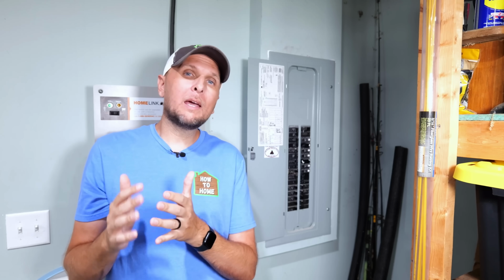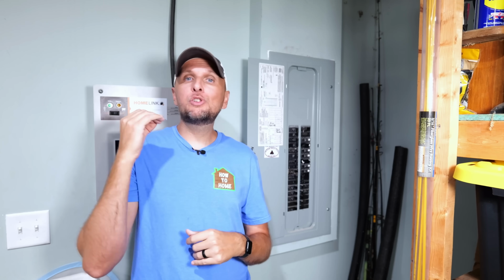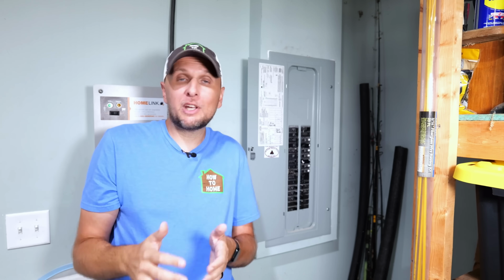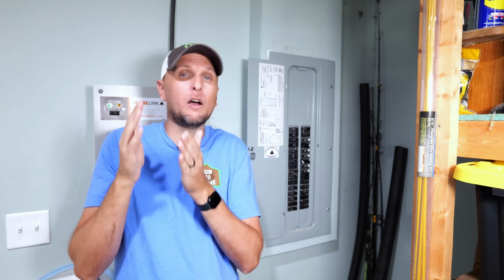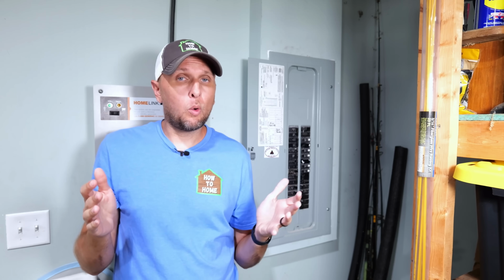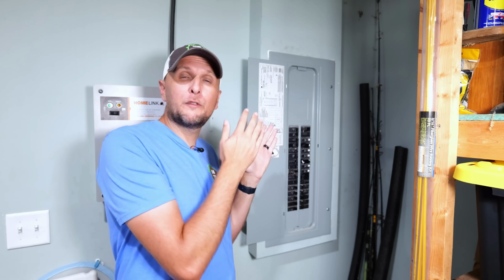For instance, a 200 amp panel should only handle about 160 amps at once, based on what's considered the 80% rule. The problem with ignoring that rule is it can bring a big risk of constant tripping or even overheating. So make sure to add up your circuits' amperage and keep it under 80% of the panel's rating. This requires knowing what the rating of your panel is.